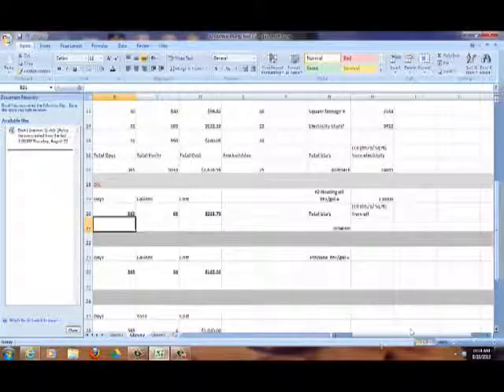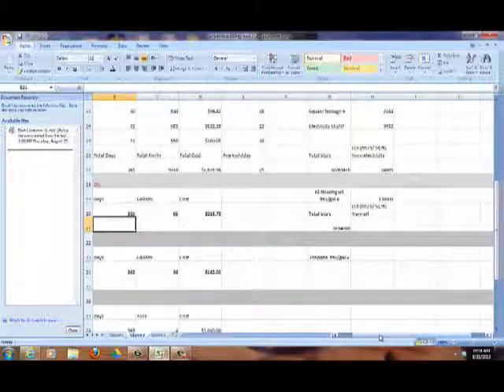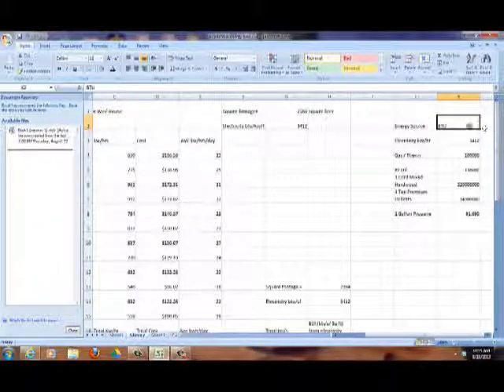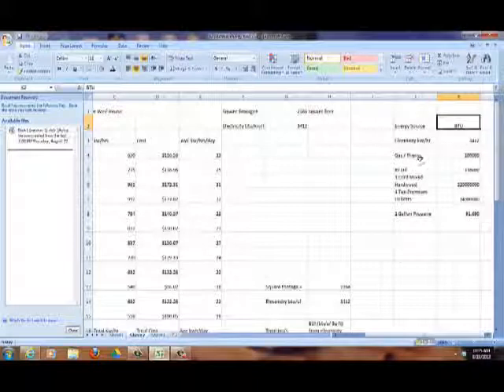Now we'll do the same for propane — I cook with propane and I used a whopping 36 gallons last year. Let's come up to the reference chart over on the right-hand side: energy source and BTU equivalent. Electricity: 3,412 BTUs per kilowatt hour. Natural gas: 100,000 BTUs per therm. Fuel oil: 138,000 BTUs per gallon. Propane: 91,690 BTUs per gallon.